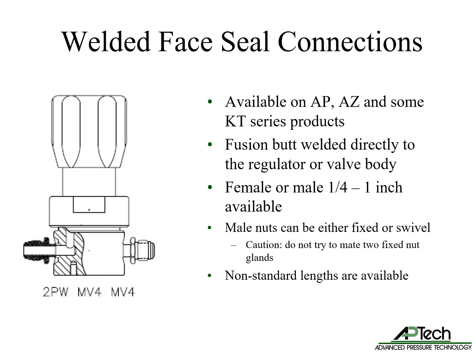The most common connections on AP and AZ series products are welded face seal connections. They are optional on some KT series products. These fittings are fusion butt-welded directly onto the body before regulator or valve assembly. 1/4 inch through 1 inch sizes are available. Male nuts can be either fixed or swivel. Users should use caution and not try to mate two fixed nut glands.